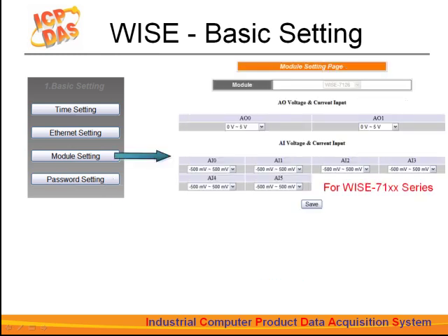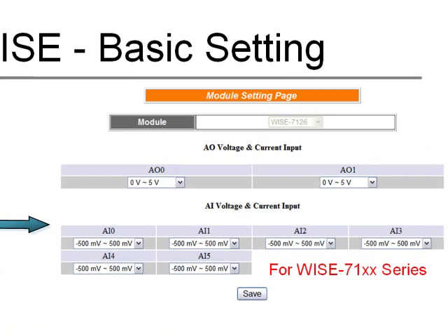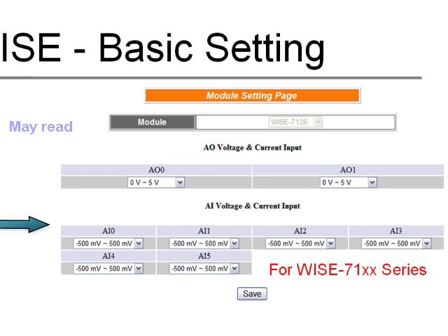Module settings can be a bit more complicated. Taking the 71XX series product as an example, different modules may come with different AI or AO channels, and they may differ in range or type. Some modules may be able to read RTD measurements; some may read thermocouple measurements. Even for the most basic operations, such as voltage reading, the settings may vary. You can set the AI range to be plus or minus 1 volt or plus or minus 5 volts, and set up different reading ranges for each channel.